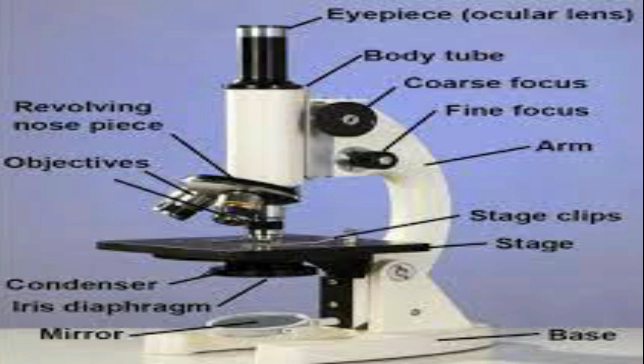The light system consists basically of an illuminator or mirror and a diaphragm or iris. An illuminator is a steady light source, 110 volts, used in place of a mirror. If your microscope has a mirror, it is used to reflect light from an external light source up through the bottom of the stage. The diaphragm or iris is a rotating disc under the stage. This diaphragm has different size holes and is used to vary the intensity and size of the cone of light that is projected upward into the slide.